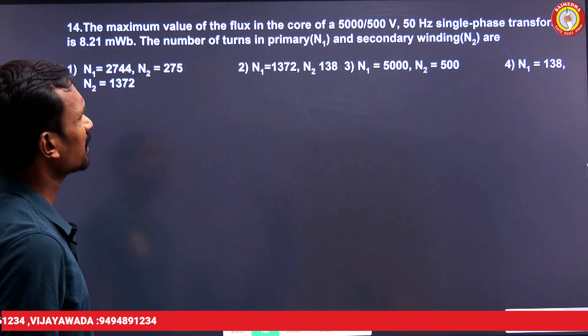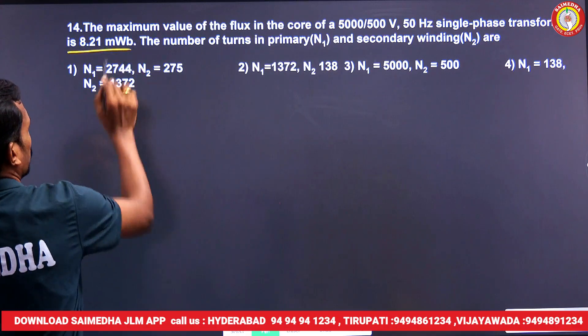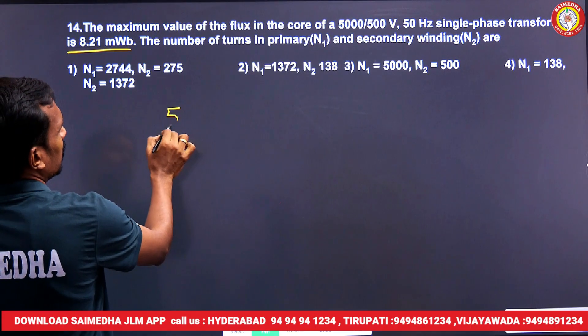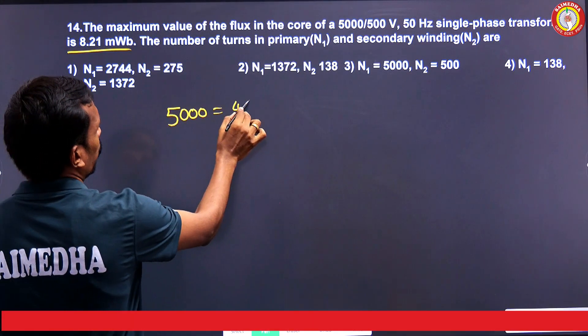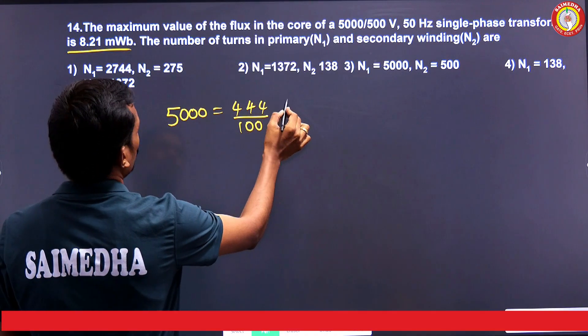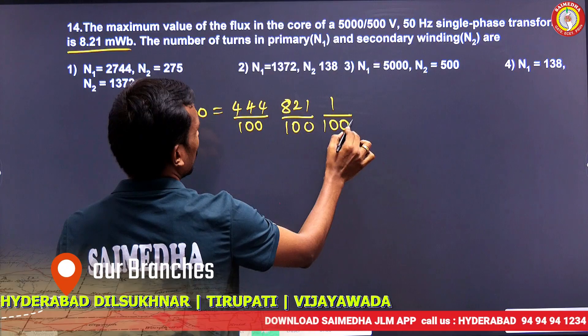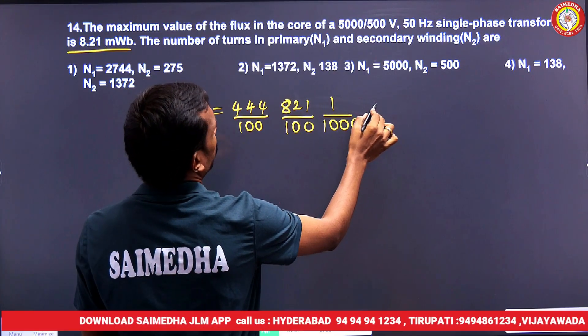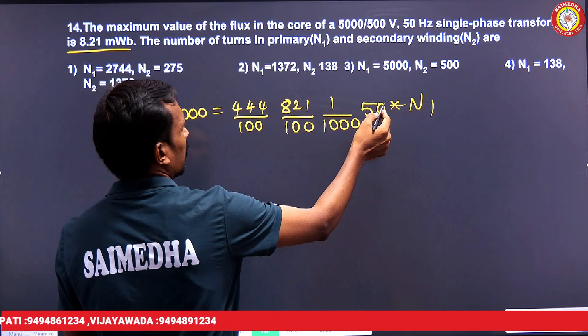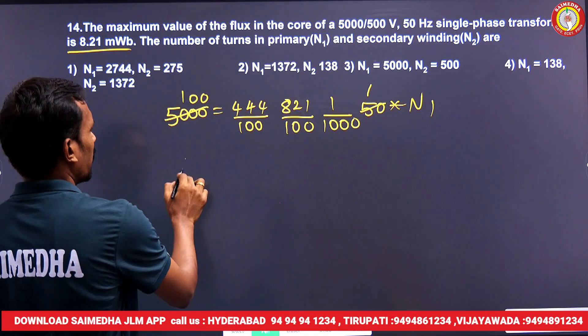Next question: the maximum value of flux in the core of a 5000/500 volt, 50 Hz single-phase transformer is 8.21 milliwebers. Find the number of turns N1 and N2. Using E1 = 4.44 × φm × F × N1, where φm = 8.21/1000 Wb and F = 50 Hz, we solve for N1.